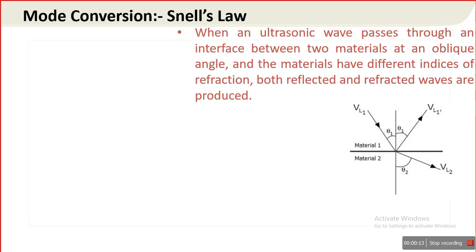So the next point is mode conversion, which is related to Snell's law. When an ultrasonic wave passes through an interface between two materials at an oblique angle, and the materials have different indices of refraction, both reflected and refracted waves are produced.